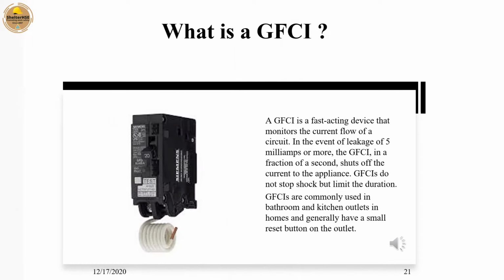A GFCI is a fast-acting device that monitors the current flow of a circuit. In the event of leakage of 5 mA or more, the GFCI, in a fraction of a second, shuts off the current to the appliance. GFCIs do not stop shock but limit the duration. GFCIs are commonly used in bathroom and kitchen outlets in homes and generally have a small reset button on the outlet.